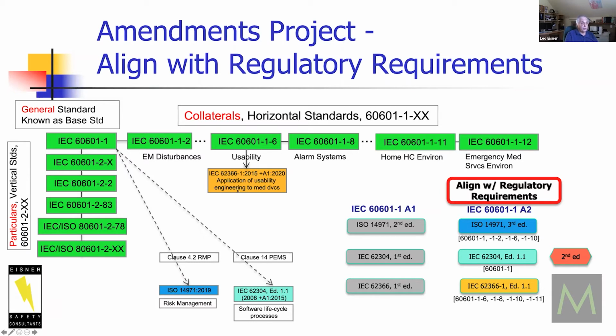This is a bridge to usability because all of these standards here are full life cycle standards. All of these standards are type test standards. So we exclude production and post-production from these standards. All the green standards do not include the full life cycle. It's only type test, meaning we're only testing once officially. You might retest a little bit to get a passing result, but you're not going through the full life cycle of the product, where you are in usability, and risk management, and software lifecycle process, which is a big distinction that some people miss. I won't say the standards like usability and 601 are perfectly written that way, but that's the intent.